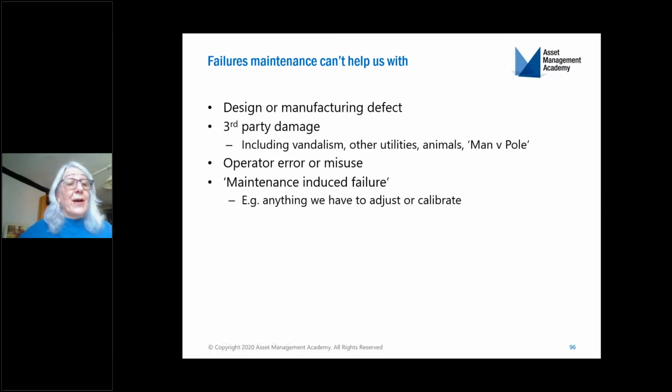That doesn't do the squirrel any good, by the way, but it's not good for the asset either. And they had a great example, a photograph of a shield, an animal abatement shield around a transformer, where the squirrels were using the shield to collect acorns. Unintended consequences, and it shorted the entire system. So animals: New York Power Authority hates beavers because their most common cause of failure of a pole in the less inhabited areas in upper New York State is actually beavers eating the poles. So there are a lot of beavers.